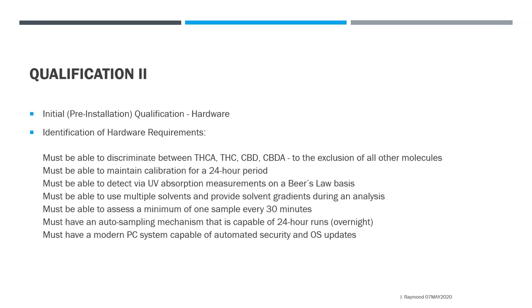Because we're using cannabis potency as our testing example — baseline potency test, HPLC with UV-Vis detector — our first requirement is that we have to be able to see the analytes and see them without overlap with other analytes. Additionally, you might determine how long it needs to maintain calibration, state explicitly how you want to detect what you want to detect and on what scientific basis, and how much flexibility you want in your system — for instance calling for multiple solvents. You may also want to state what rate of throughput is your absolute slowest acceptable, and state things about auto sampling or add-ons that allow batch size control and run control.